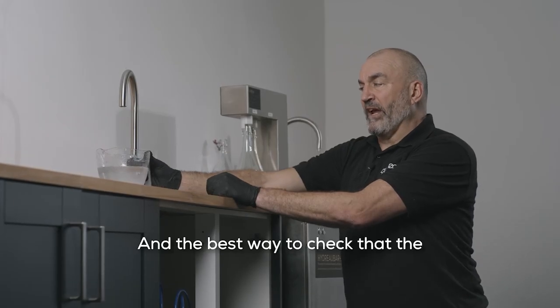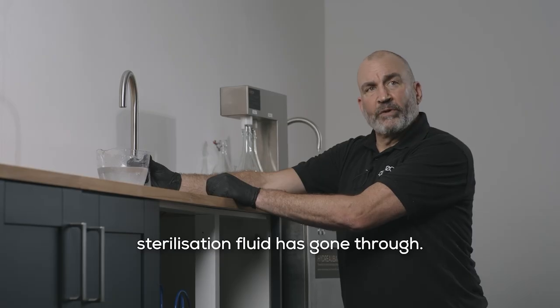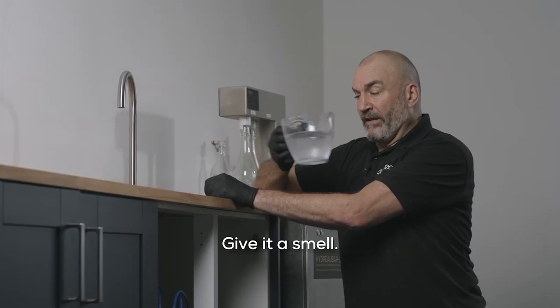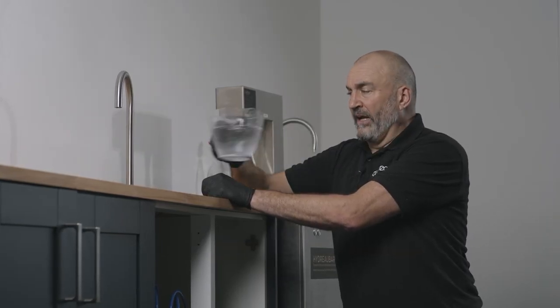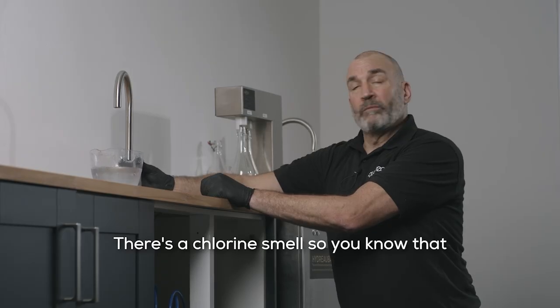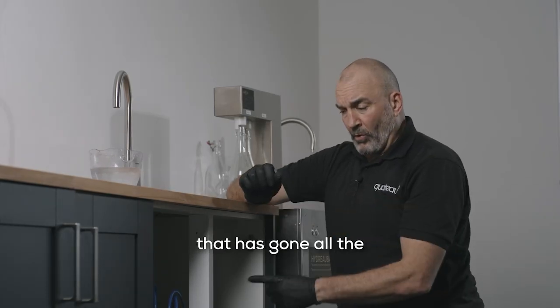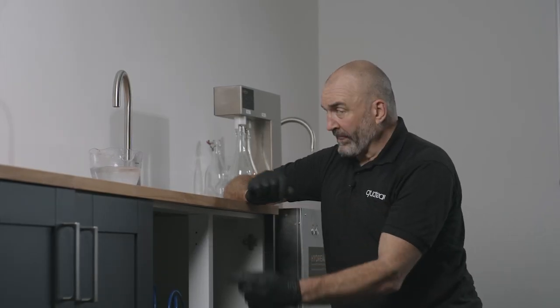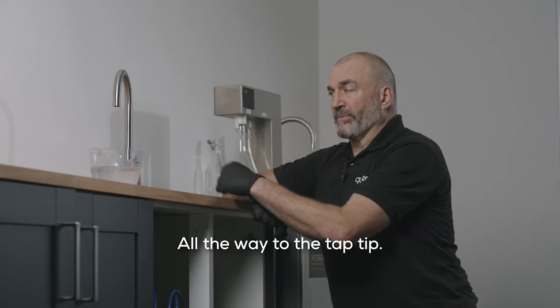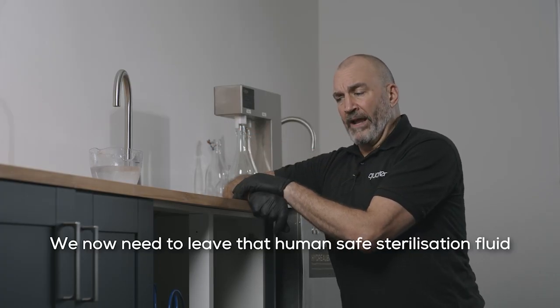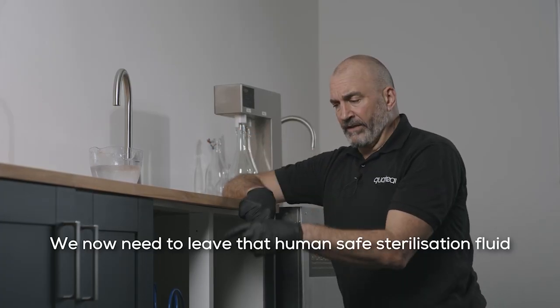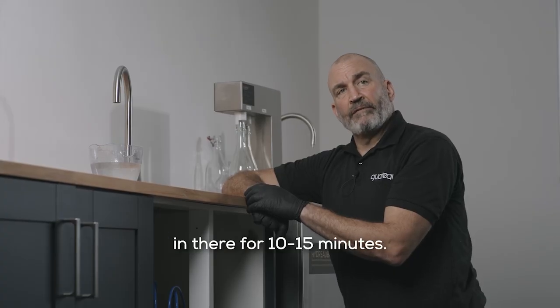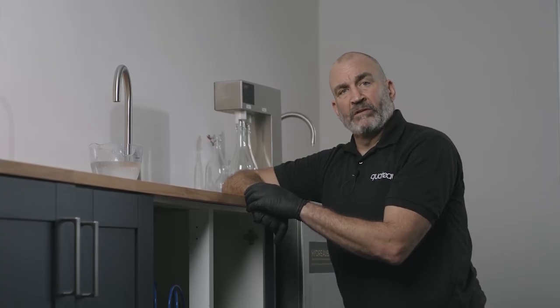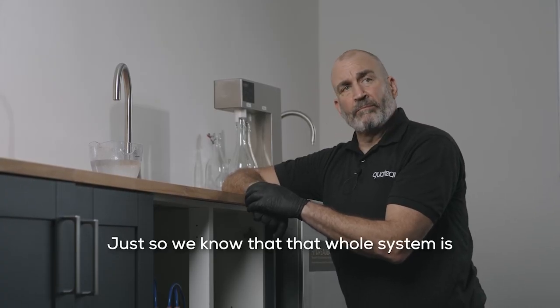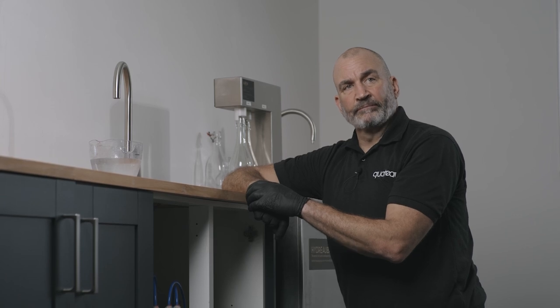And the best way to check that the sterilisation fluid has gone through, give it a smell. There's a chlorine smell, so you know that that has gone all the way through the system, all the way to the tap tip. We now need to leave that human safe sterilisation fluid in there for 10-15 minutes, just so we know that that whole system is completely sanitised.